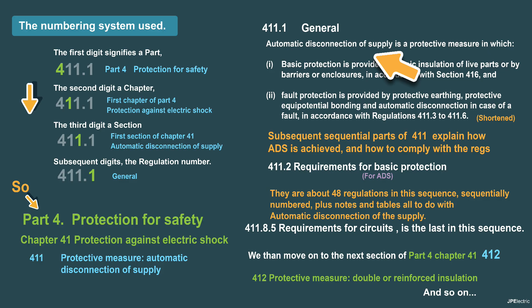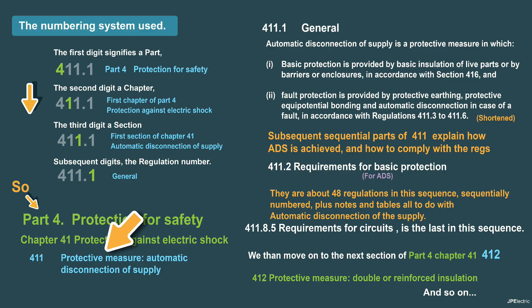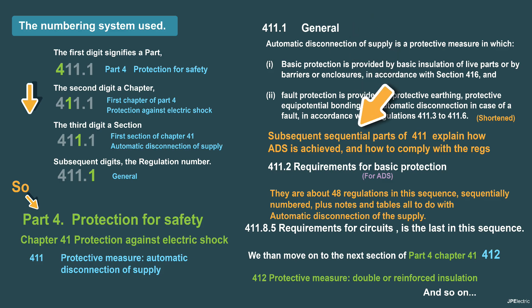And that is general, and you can see it here. Automatic disconnection of supply is a protective measure. So it goes part 4, chapter 41, 411, 411.1. Then subsequent parts of 411 explain how ADS is achieved. So 411.2 is a requirement for basic protection for ADS. There are about 48 regulations in this sequence, sequentially numbered, plus notes and tables, all to do with automatic disconnection of the supply. 411.8.5, requirements for circuits, is the last in this sequence.